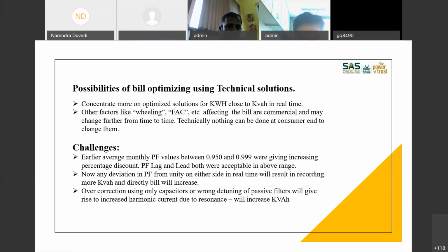Do it within the budget available to you and within the available solutions. So that's what one needs to do. What are the challenges? Earlier, for average monthly PF values from 0.95 to 0.99, we were getting stage-wise discounts and incentives. So any small achievement brought some gain. Now there will not be anything like this. The moment your power factor is less than unity or more than unity, on either the lagging or the leading side, your bill is going to increase. You cannot back-correct it anymore.